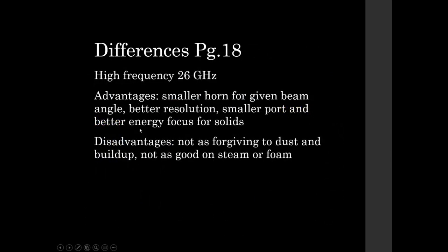The advantages of these high frequency devices are a smaller horn for a given beam angle, which brings us better resolution, smaller port sizes in the vessel, and better energy focus for solid applications. Disadvantages here, they're not as forgiving to dust, foam, and buildup. So you see here they have different applications, and these are great test questions, of course. Most of the questions in here are going to be application-based.